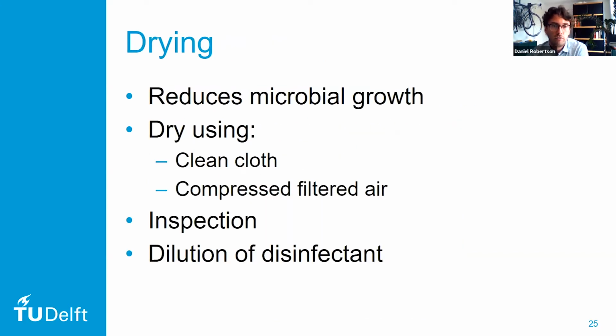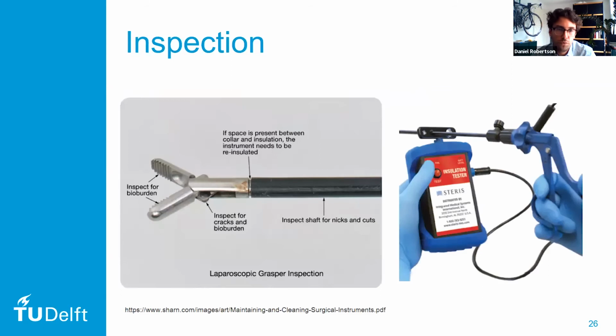Now, the next step after cleaning is drying. And the aim of drying is that it reduces the microbial growth after cleaning. And you'd want to dry your instruments using a clean cloth, and you can use compressed filtered air to dry the lumen of the instrument. And this is why we suggested having compressed air in your reprocessing facility. Now, drying is also important if you want to inspect your instrument after cleaning. And the last important aspect about drying is that if you're using any type of liquid disinfectant after the cleaning step, when you're adding wet instruments, you're continually adding dilution to the disinfectant, and it will reduce its effect before the manufacturer's date. So what should we look for during inspection?